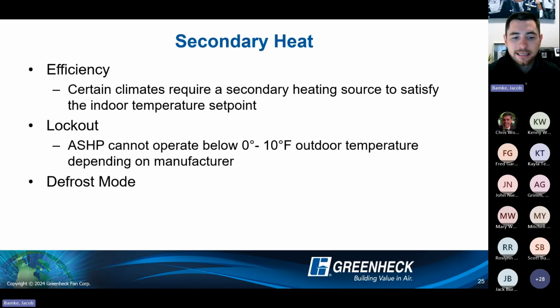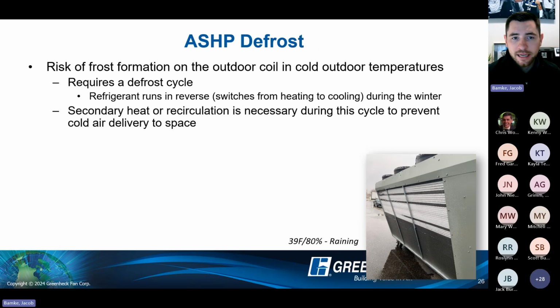And then lastly is that defrost mode. And so defrost happens when you have the outdoor coil that's grabbing all this heat in, and now we have this frost buildup that you can see on the right-hand side. And this was an actual tested unit that happened at 39 degrees outside, about 80% relative humidity because it was raining. So if I were to guess, that happens quite often in the winter months in the Washington area. So fairly mild temperatures, you get some rain. This could happen, and you need the refrigerant cycle to run in reverse.